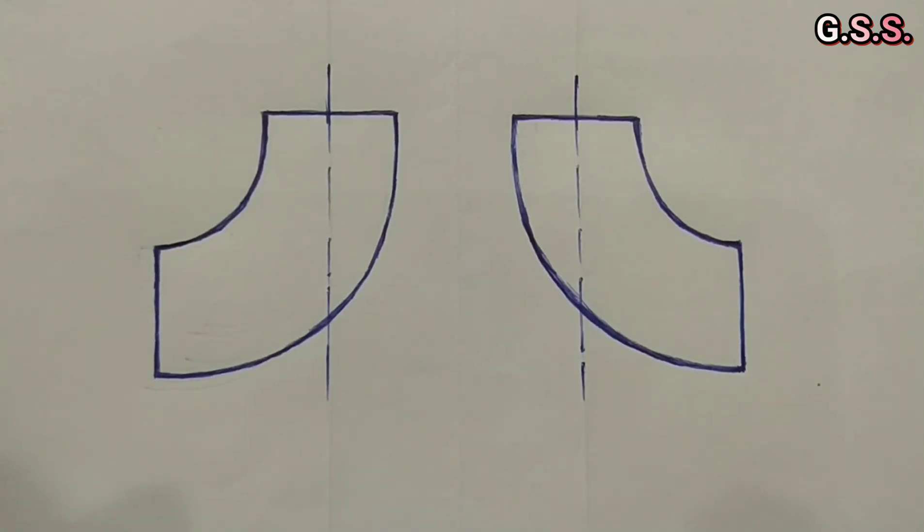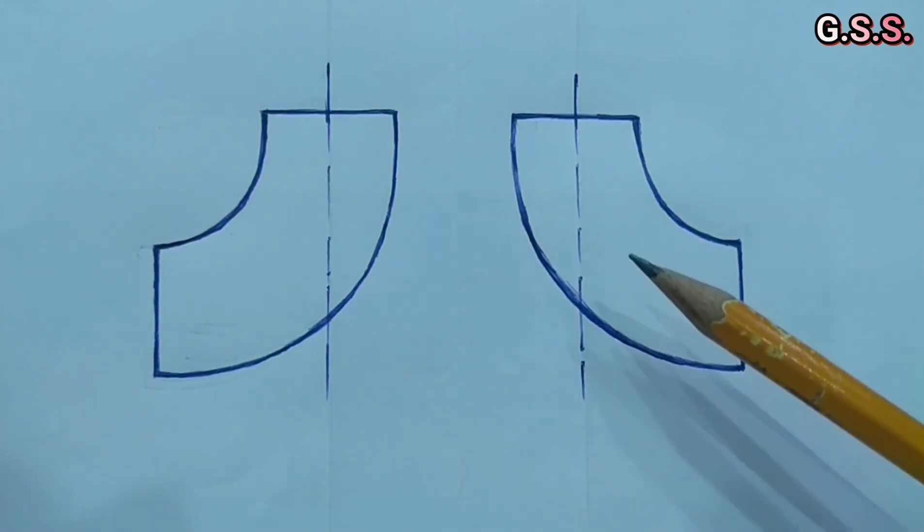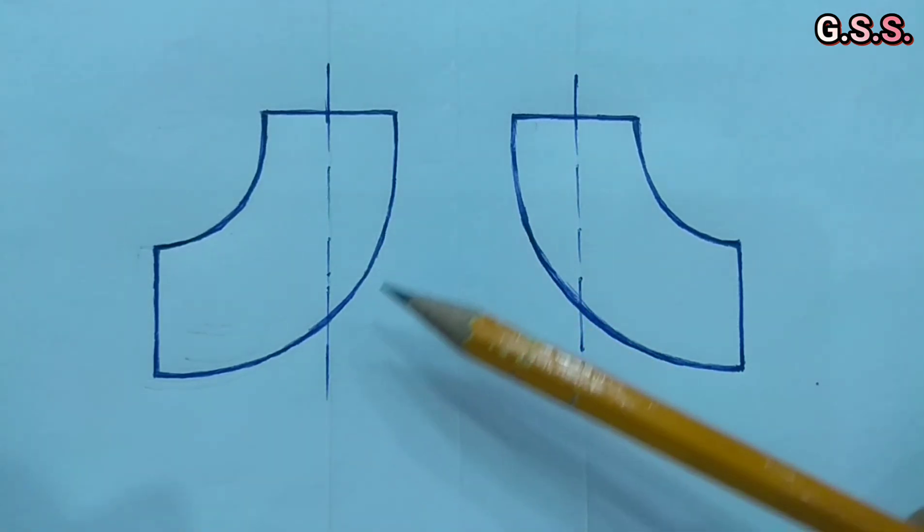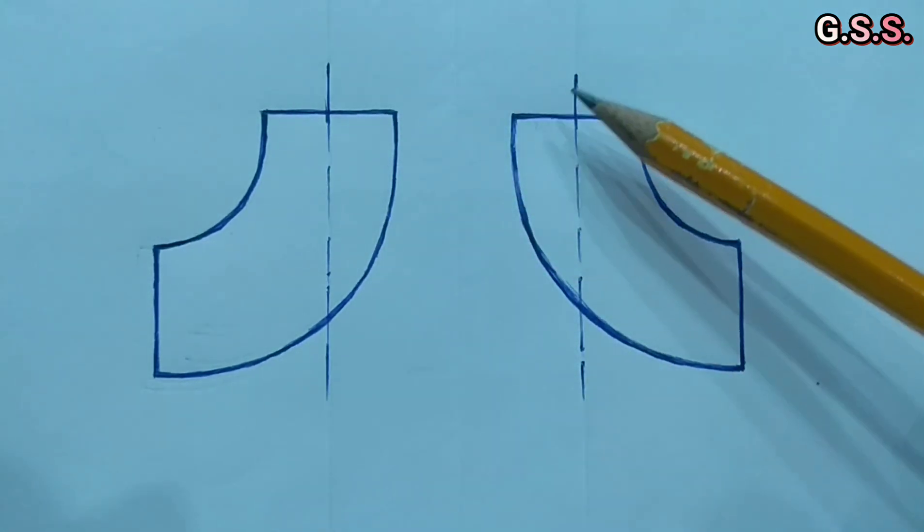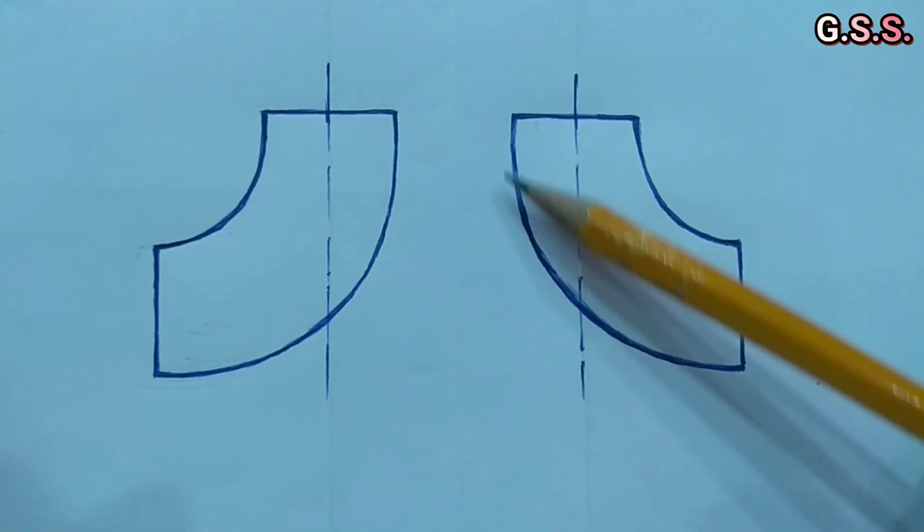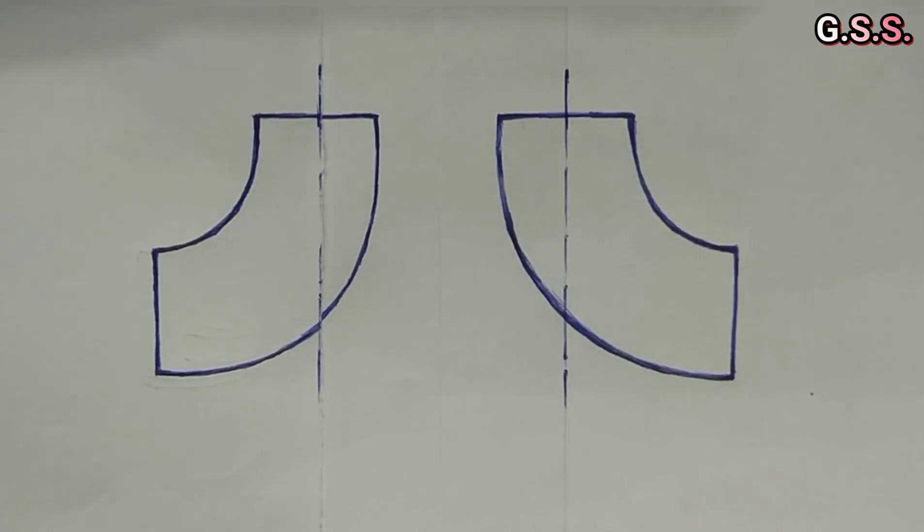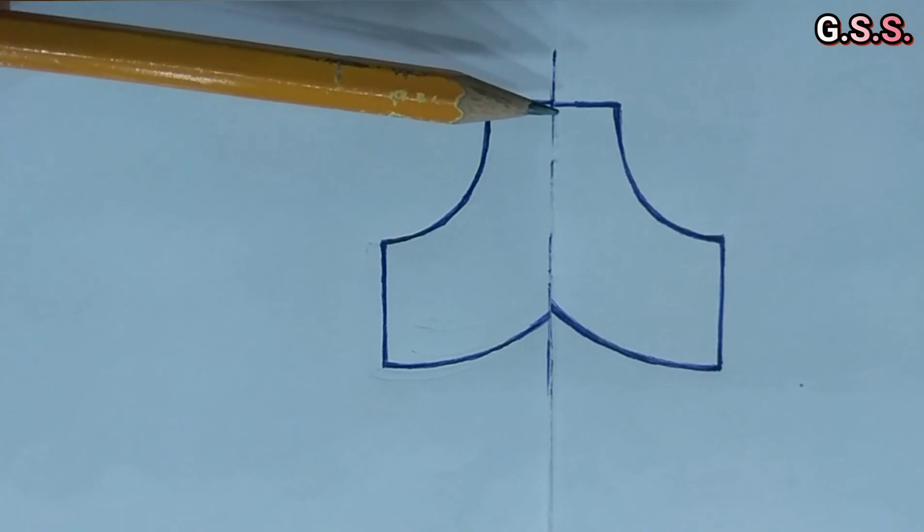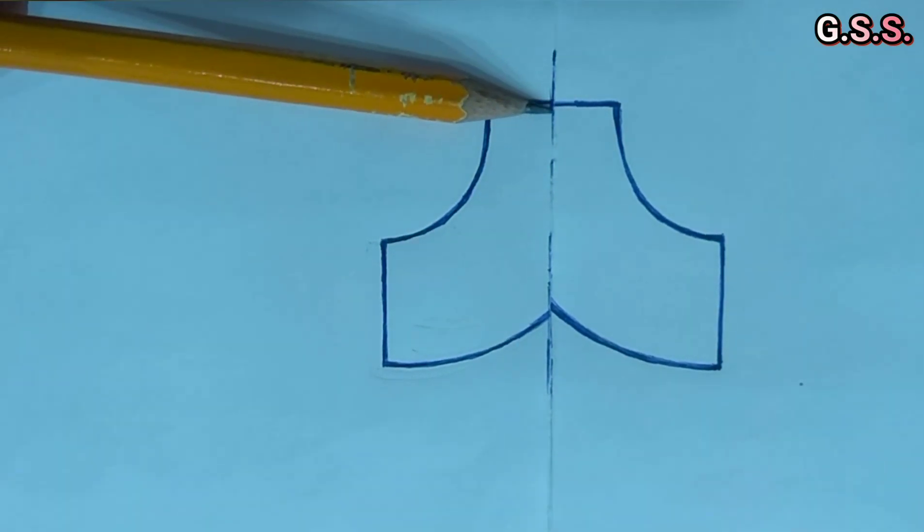Now we will see how to make elbow T or sweeping T from two elbows. These are two elbows and we have to cut and remove this portion from center line of this elbow and this portion from center line of this elbow. Then we make elbow T or sweeping T after joining and welding these two elbows.